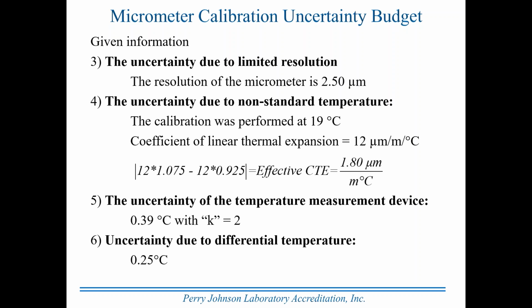Just arrive at it by a reasonable analysis of temperature conditions and the comparative ratio of the mass of one to the mass of the other, and come up with a number that you then apply all the time. Be prepared to defend it. So if you do some study and look at what the maximum displacement would be, what the minimum is going to be, and what you are going to use, I would advise you to write that down, document it, and keep it on hand, because if an assessor ever says, well, where do you come up with this, you can defend your choice. Most assessors are not going to say 0.25 is way too small or way too large. They're simply going to be looking for the fact that you have a value and that it makes sense. And it makes sense on the basis of defending it with the documentation you retain.